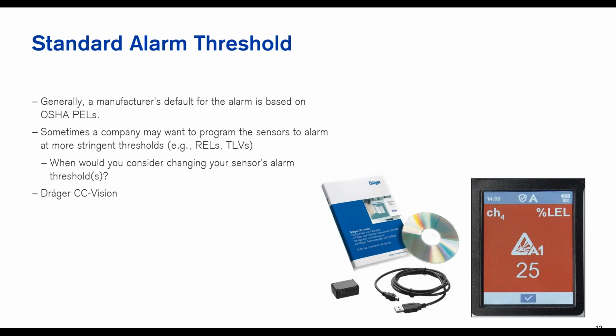And so let's say we're using a catalytic bead sensor, your Wheatstone bridge, and we're in a situation above the LEL. Those catalytic bead sensors will only read up to 100% of that LEL. So if I'm reading, let's say methane, just to keep it simple here, I know I'm looking for methane, and methane LEL, the lower explosive limit, is 5%. It will only read up to 5% of that concentration. And once it hits that 100% LEL, which is 5% of the concentration, it's going to stop.